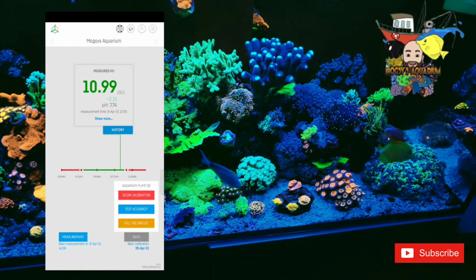Before you do any calibration, guys, you must fill the circuit. So you press the fill the circuit button. That then pumps the water through this actual machine, through the system, and once it starts to come out of the pipe, that's when you know you can begin the calibration process. And the same thing applies. Once you've done it, it basically tells you your accuracy, and it says the same.